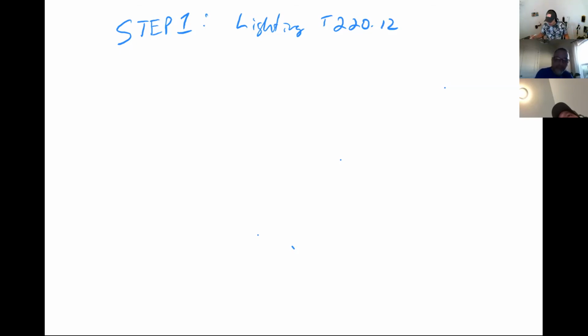There's a reason for that. If you look at the table on the left-hand side, about seven rows down, you see dwelling units listed there. This table is general lighting loads by occupancy, but for dwelling units, as well as hotels and similar places, you see the little letter A at the end? What they're telling you with that note is that it also includes all of your receptacle loads in the dwelling that are part of the non-required circuits. In other words, in a bedroom in a house, I've got to have a receptacle within 6 feet of the door.